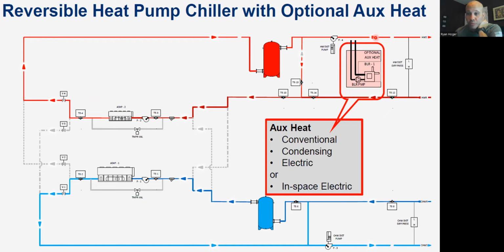You could use an electric boiler because someone says, I want to have an all-electric building. But in that case, you probably really want to think about, should we spend more money to put in bigger coils and radiators instead of getting this ginormous electric boiler? Because that would be pretty rough, making 180 degree water with an electric boiler for the whole building. But in any case, you could choose whatever heating source you want: gas-fired boiler, condensing boiler, inefficient boiler, electric boiler, waste heat off of some kind of process, whatever you've got to dump heat into this loop.